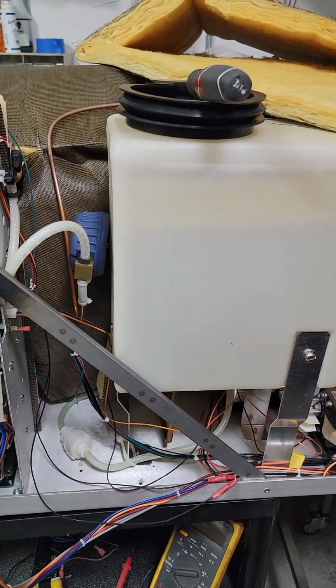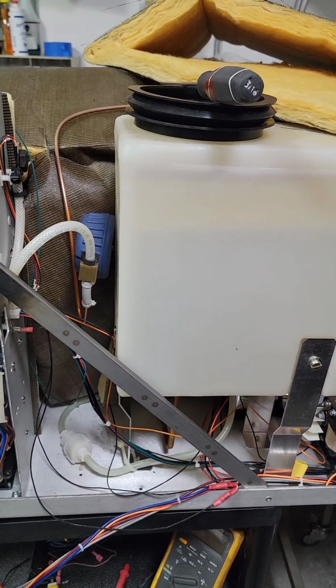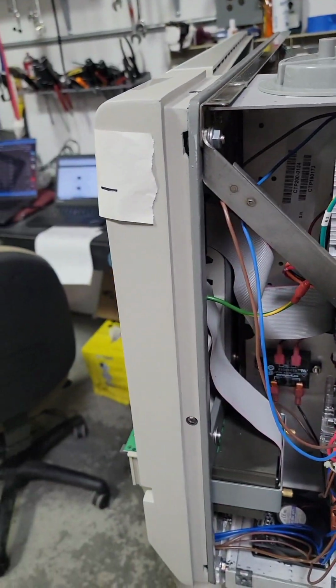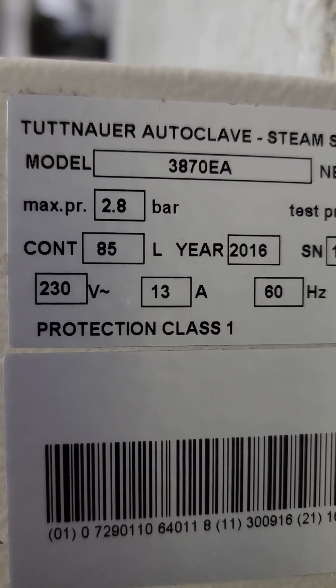So, start with the KISS principle. Keep it simple, stupid. Check the obvious. There's a sticker on the side of the unit, right here, to confirm: 230 volts. There you go. Okay? So start there. Now, to do the calibration, first thing I like to do is attach a gauge.